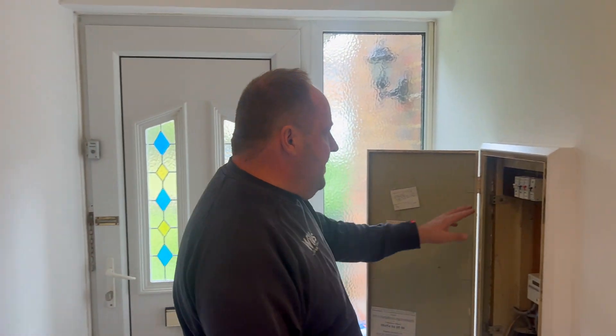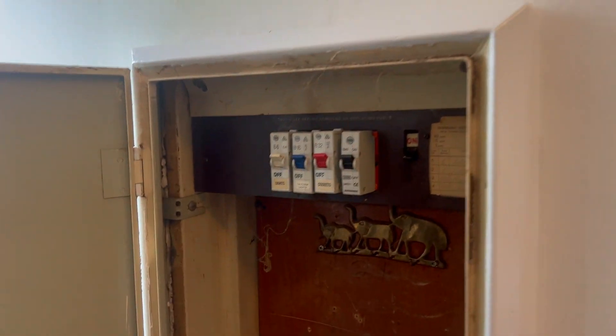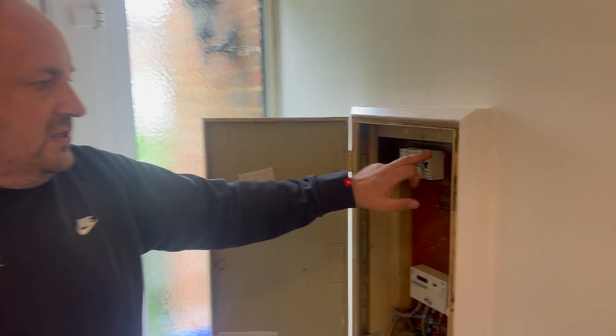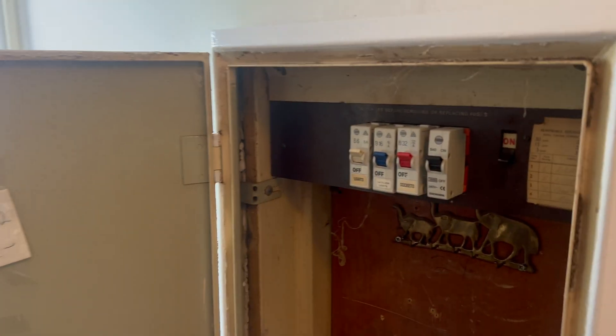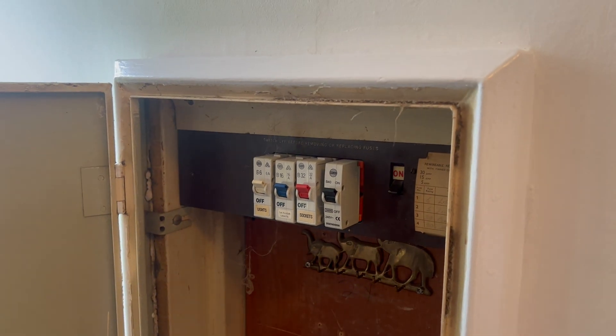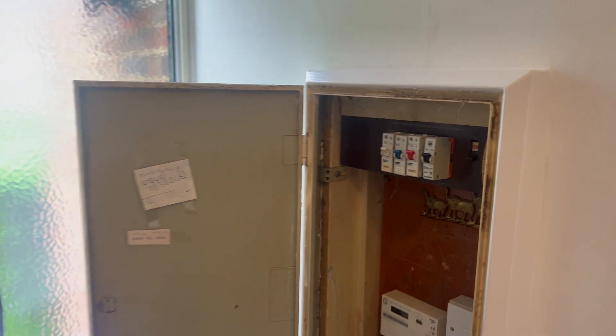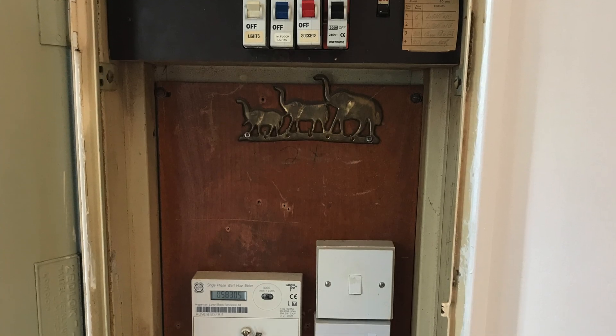The other observation you're going to get from this is there's no RCD whatsoever, so none of the sockets could be used outside, or any of the circuits buried 50mm or less within the wiring zone. You've got a 40 amp breaker there. You'll probably find that's on a 6mm buried cable, and I think the maximum for a buried 6mm is 32 amps. But we'll quickly go through it all.